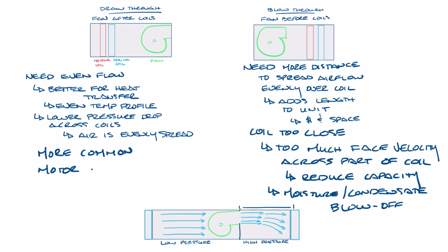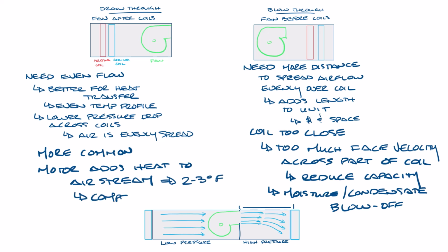Another thing to consider in a draw-through arrangement is the motor adds heat to the airstream just as it's entering the ductwork. This can add 2 to 3 degrees to the airstream. And you may need to compensate for this by having the air leave the coils a little bit cooler.